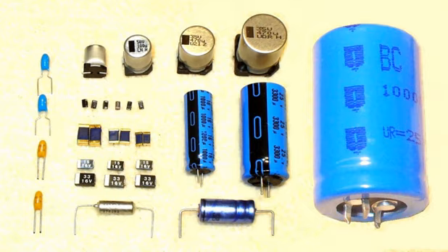Individual components fail at random times but at a predictable rate. Billions of tested capacitor unit hours would be needed to establish failure rates in the very low level range which are required today to ensure the production of large quantities of components without failures. This requires about 1 million units over a long time period, which means a large staff and considerable financing.